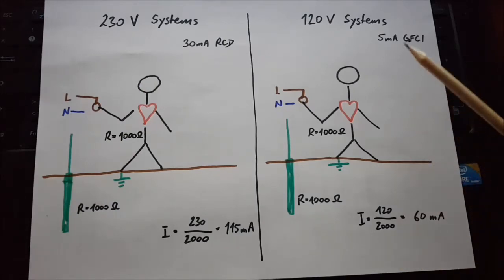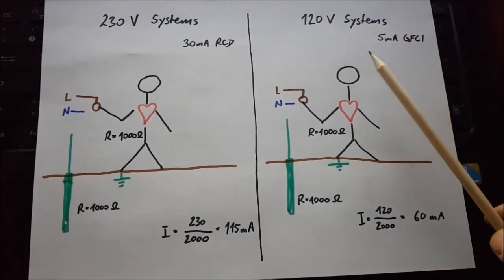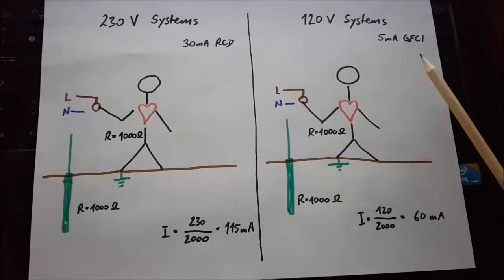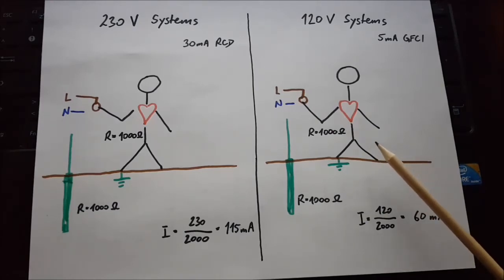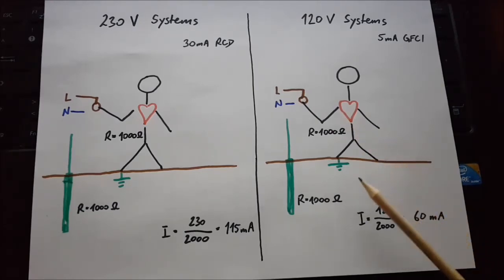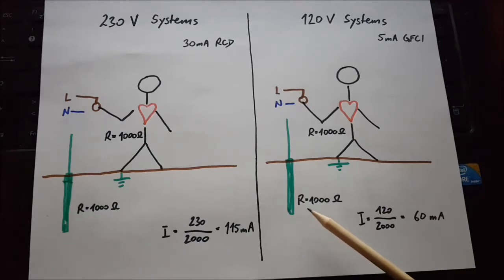How does it look in the 120 volt system, which is protected by a 5 milliamp GFCI? We have the 1000 ohms resistance of the human, same to that one. We have our impedance 1000 ohms on our grounding system. 120 divided by 2000 equals to 60 milliamp leakage current. So 60 milliamp against 5 milliamp.